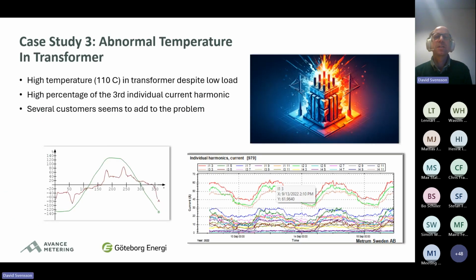Picture this: a substation with 3 transformers running hot despite a minimal customer load. The culprit: excessive third current harmonic. Multiple customers exhibit this harmonic signature, making it even more complex. We are still working on this case to figure out the root cause, but I have some idea where the harmonics come from. These 3 cases I've shown you illustrate the critical importance of understanding, detecting and addressing customer-generated harmonics.